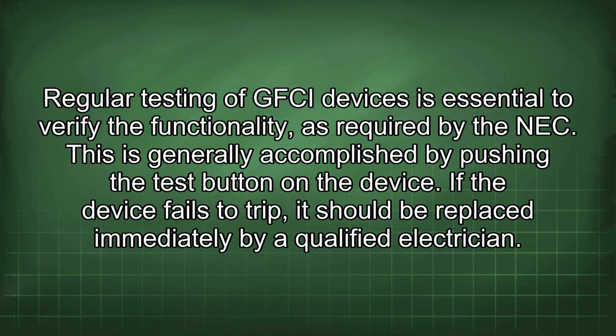Regular testing of GFCI devices is essential to verify the functionality as required by the NEC. This is generally accomplished by pushing the test button on the device. If the device fails to trip, it should be replaced immediately by a qualified electrician.